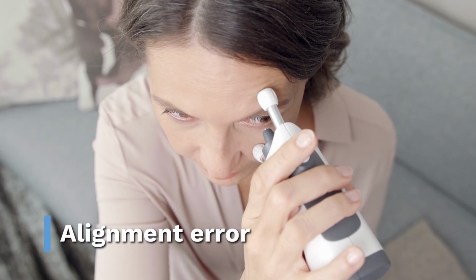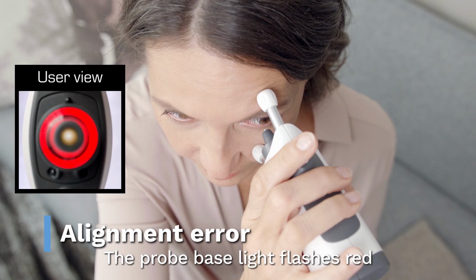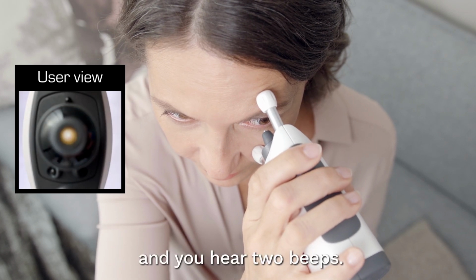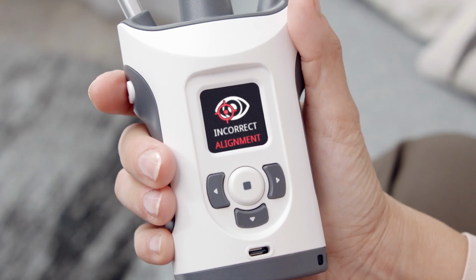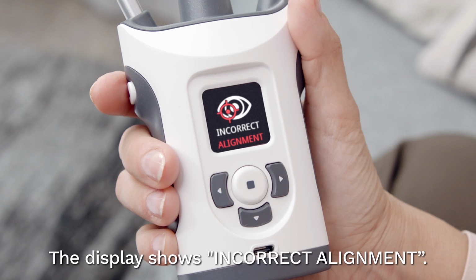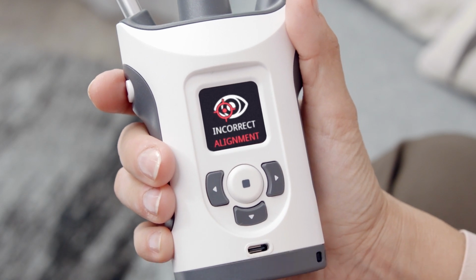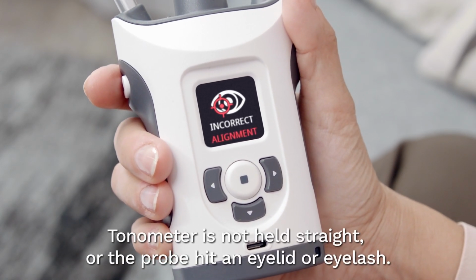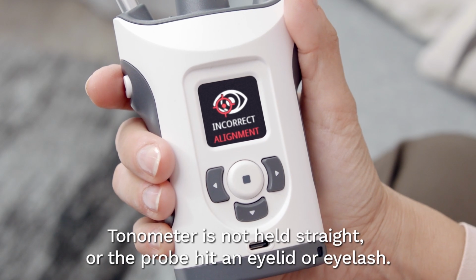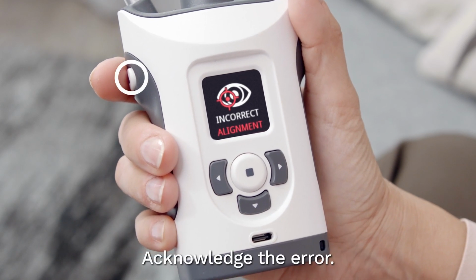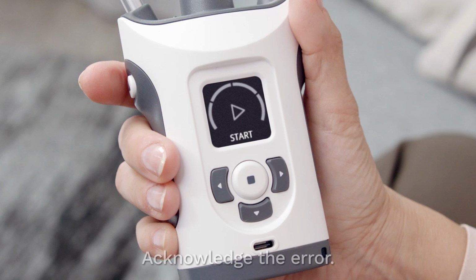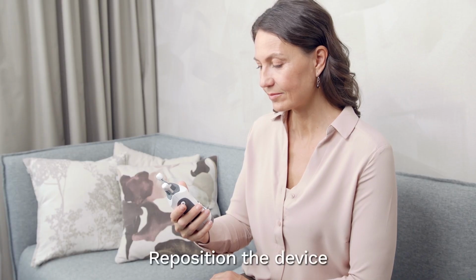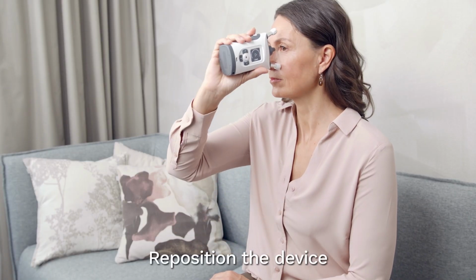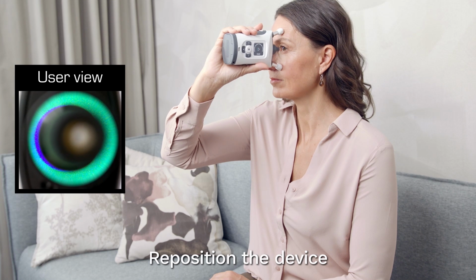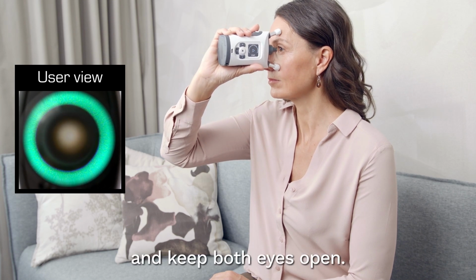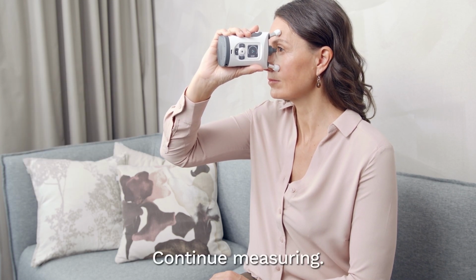Alignment error. The probe base light flashes red and you hear 2 beeps. The display shows incorrect alignment. The tonometer is not held straight, or the probe hit an eyelid or eyelash. Acknowledge the error. Reposition the device so the probe is perpendicular to the centre of your eye, and keep both eyes open. Continue measuring.